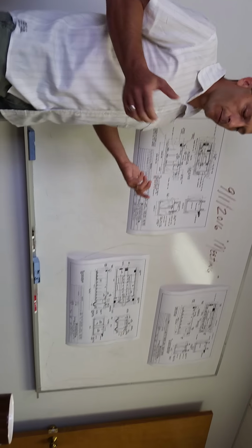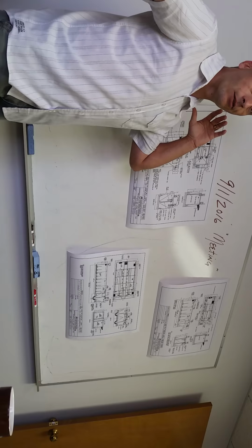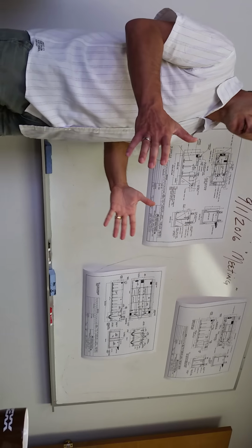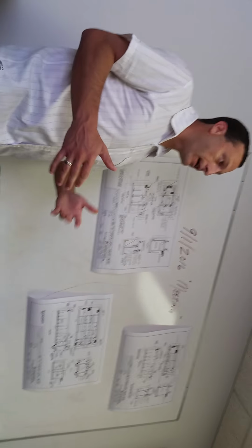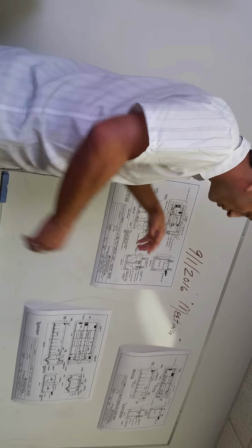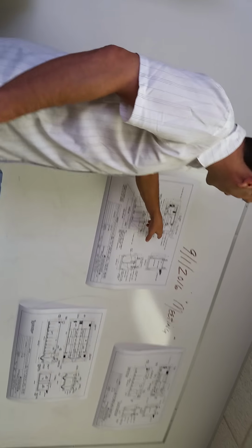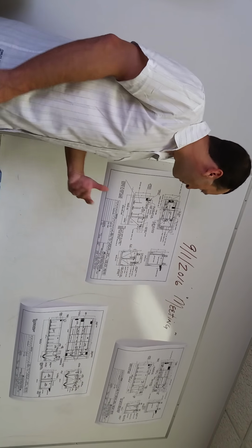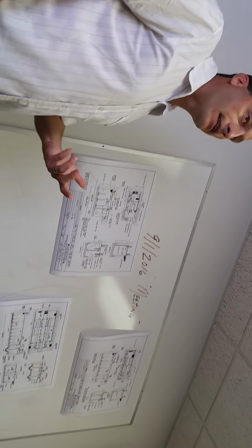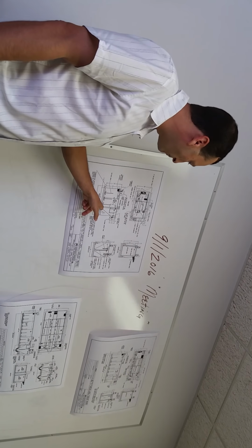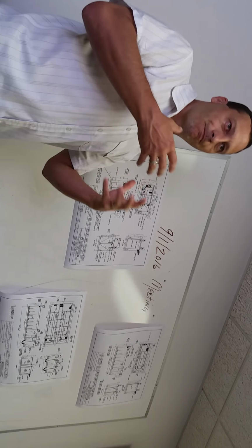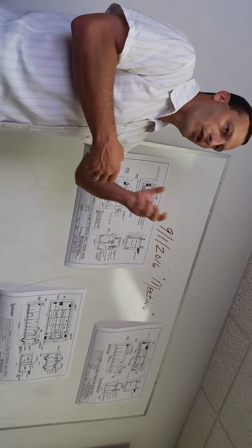So the operator is going to have a big handled squeegee, for lack of a better word, out there, and once a day or once every other day he's going to have to go out, stand up on top here, and shove down the solids that have accumulated on the side of this clarifier. What can happen if he doesn't is because we're not running a very high recycle rate here, it's not a strong suction that we're pulling.